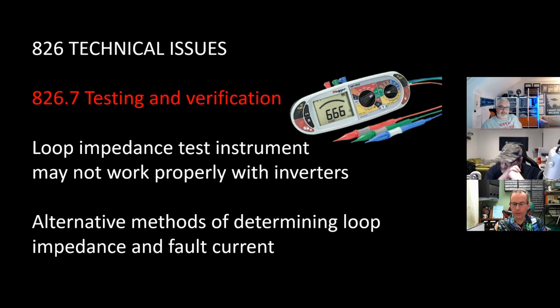Another problem with this is that the loop impedance itself will change depending on what mode you're in and what actual energy sources are coming in. So it's definitely not going to be a question of plug it in and do the test and that's it. It's going to be plug it in and then check which mode you're in, do a test in that mode, temporarily switch it to the other mode, do a test there, put different types of generation coming in, your solar's coming in, your batteries are coming in. So there's going to be a lot more testing, or this sort of suggested alternative. But the problem with alternatives is if you're going to calculate it, it's only going to cover a very specific situation and it could be wildly off.